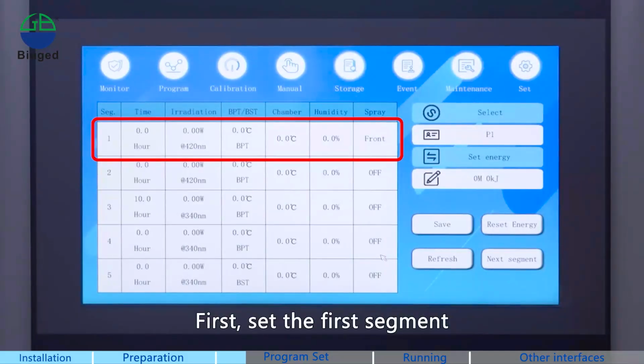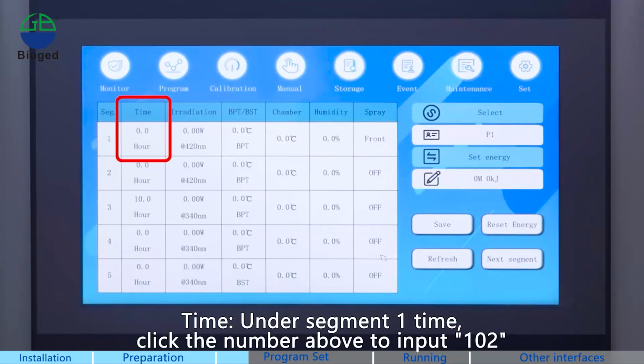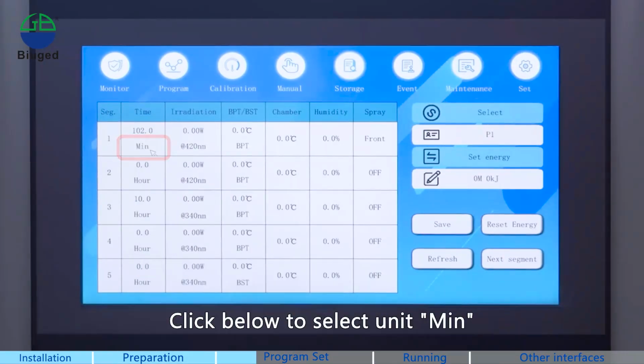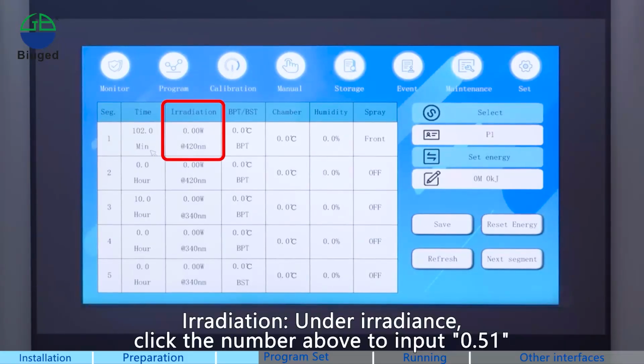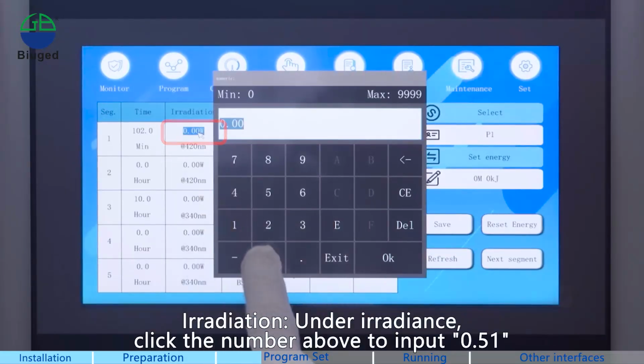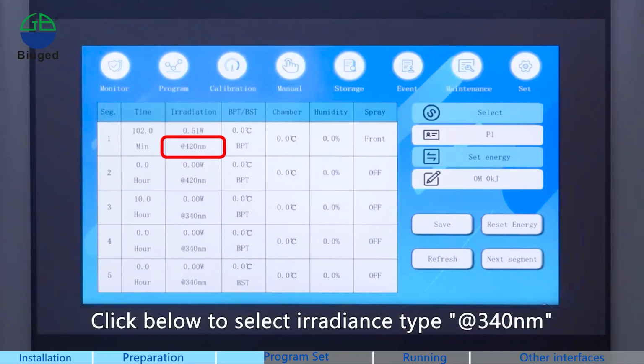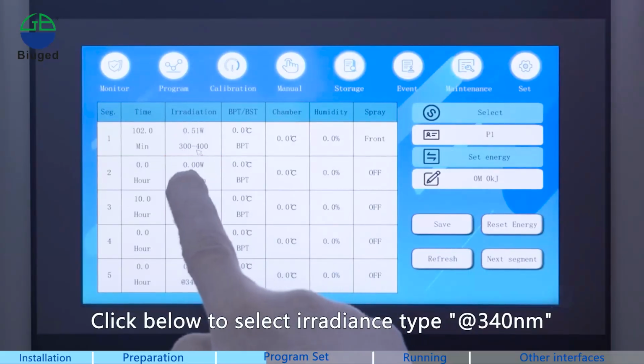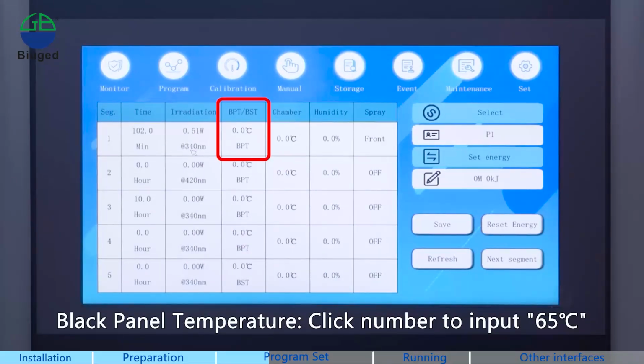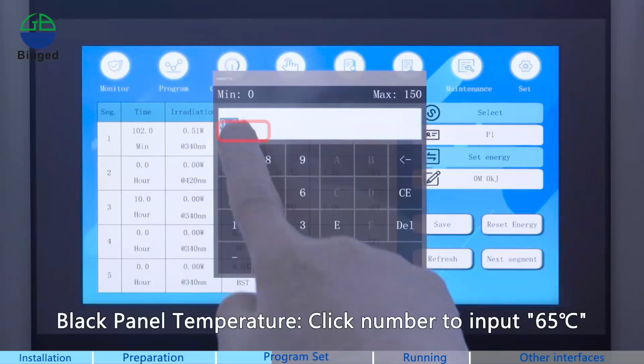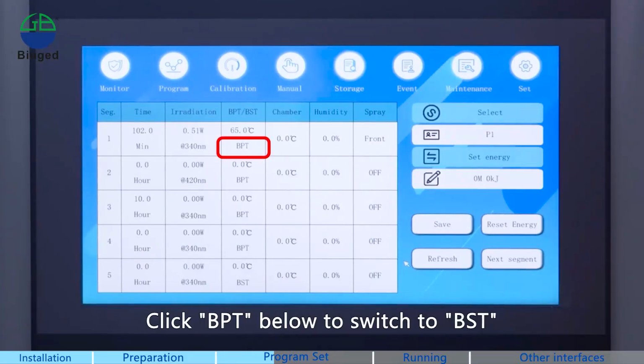First, set the first segment. Time, under segment 1 time, click the number above to input 102. Click below to select unit min. Irradiation, under irradiance, click the number above to input 0.51. Click below to select irradiance type at 340 nm. Black panel temperature, click number to input 65 degrees Celsius. Click BPT below to switch to BST.